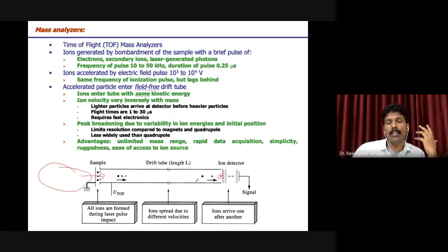So, time of flight. This analyzer measures the point of time at which these ions enter the analyzer, and the time at which the detector detects them. So the time taken for an ion to reach the detector will be measured. That is why it is said to be time of flight. In the flight tube, the fragmented ions are freely moving and reaching one by one, just based on their inherent property. Lighter ones have more velocity, and they reach quickly as compared to the heavier fragmented ions.